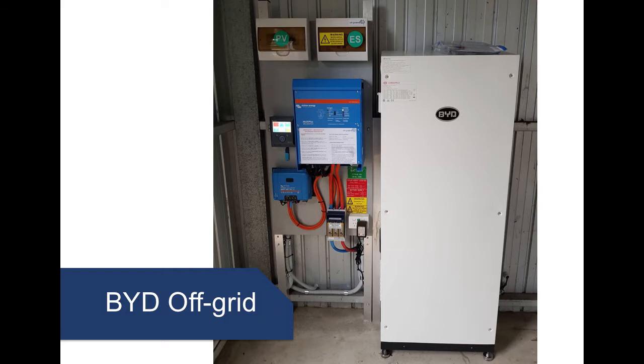We installed a 5 kilowatt SP Pro, and we had a 5 kilowatt Fronius inverter, but she was wanting more than 10 kilowatts of solar. We worked through with AusNet, and they wouldn't allow us to put any more than a 5 kilowatt solar inverter with the 5 kilowatt battery inverter. So we DC coupled some additional solar in to get around that requirement or restriction from the grid distributor. Yeah, it's quite interesting if you can get the system set up and working.